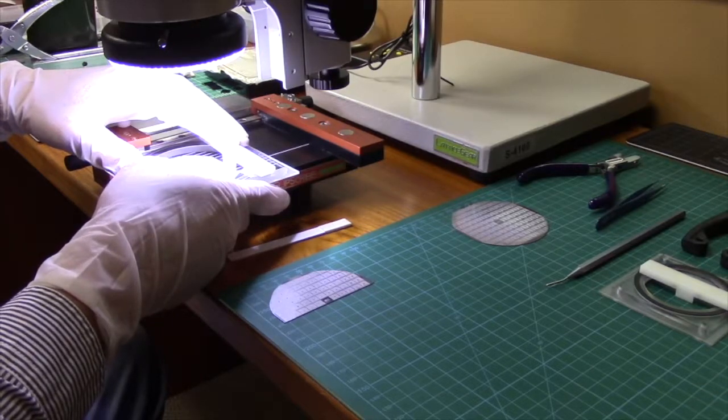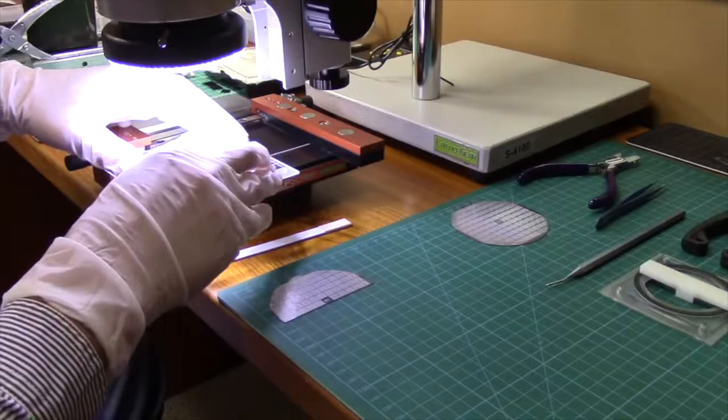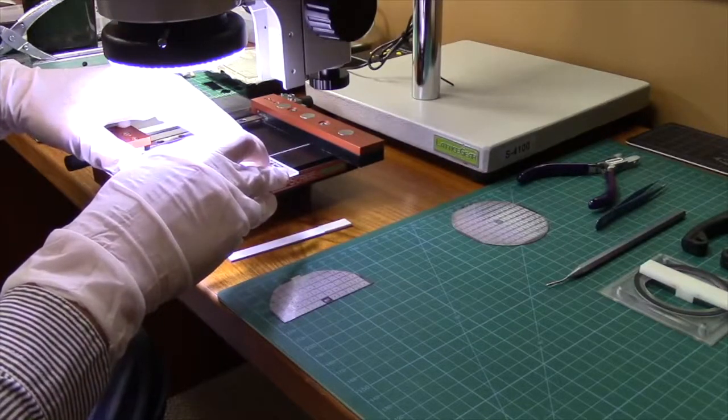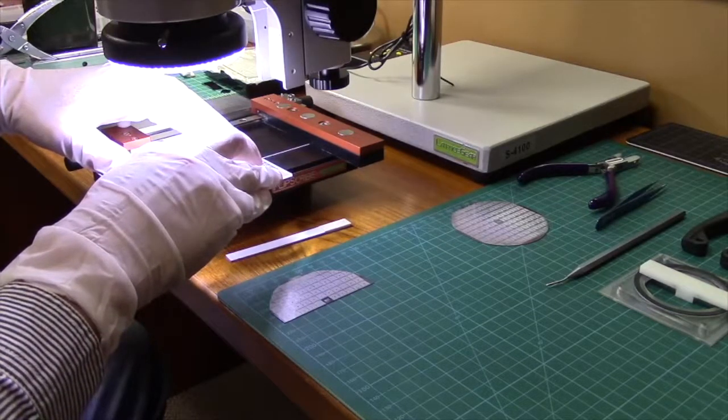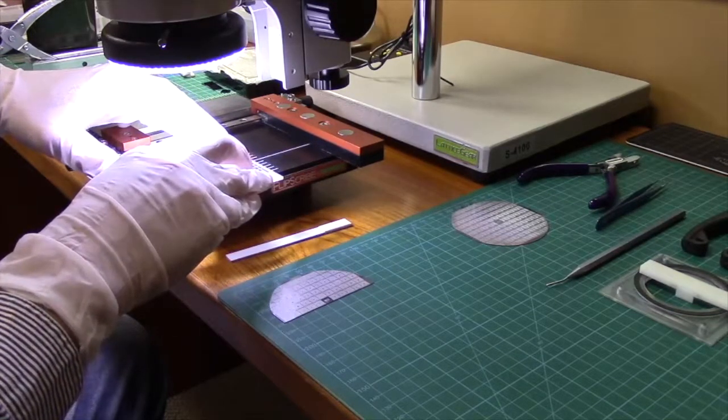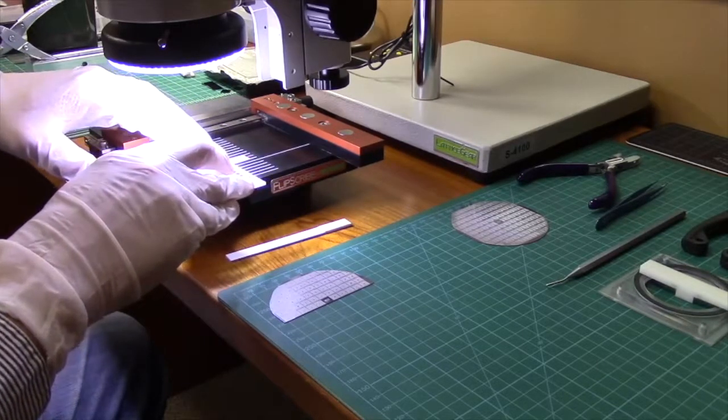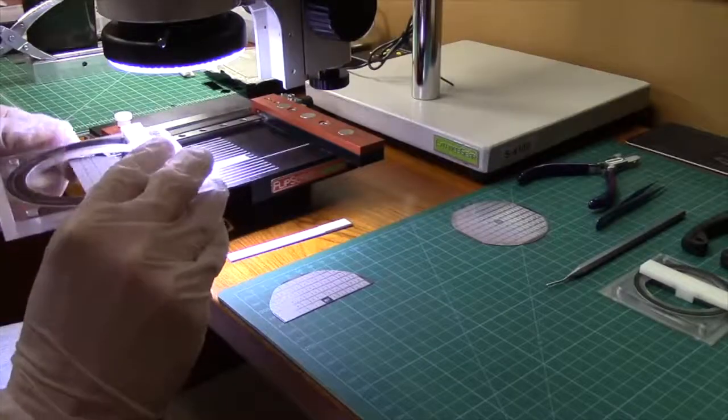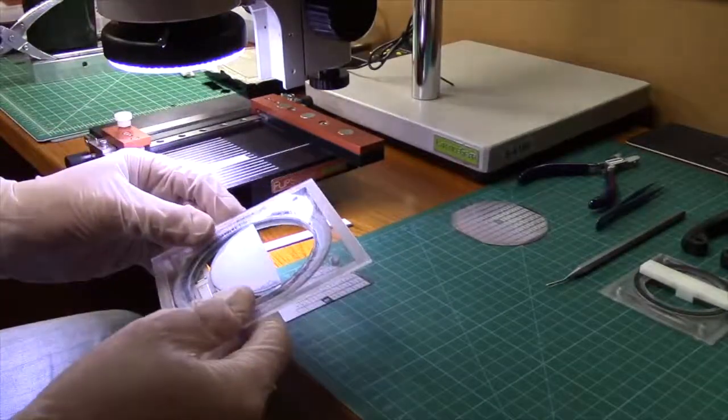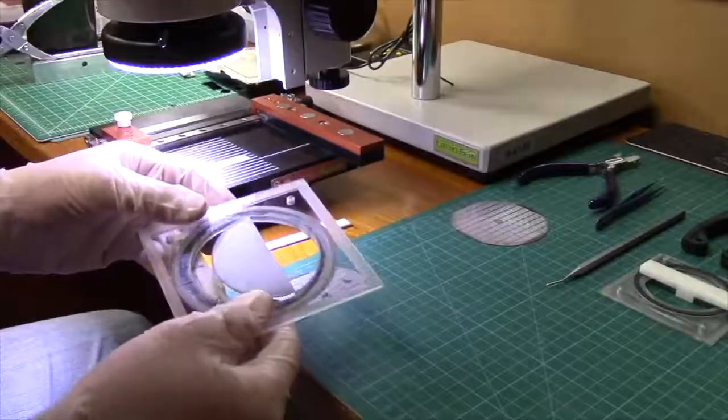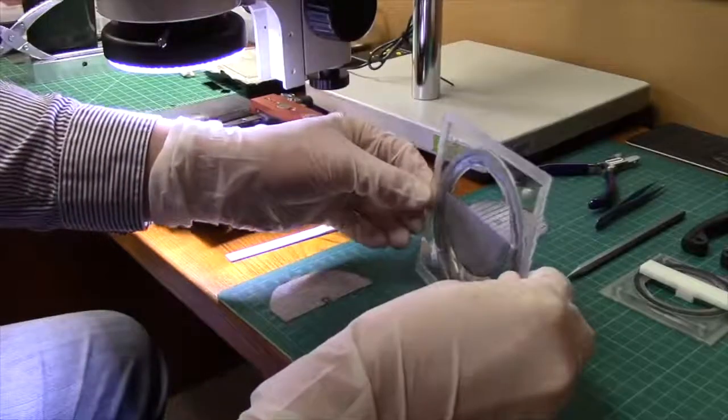The back side scribe will be made across the whole of the wafer. Press the wafer holder firmly on the sides while having a finger on the top white bar. Then slowly slide along the platform using the guide bar to keep the scribe straight. The sample should easily glide over the scribe tip and an audible slight scratching should be heard over most of the scribe length.